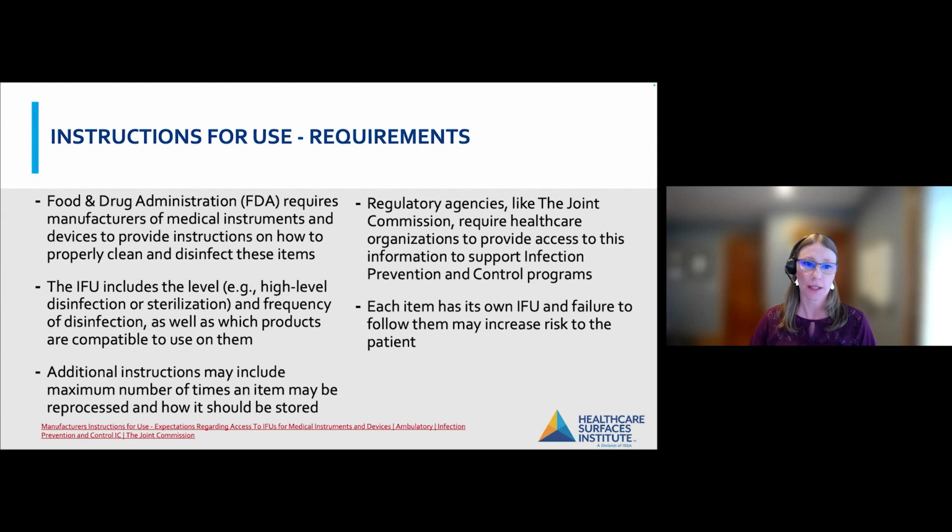There's a specific endoscope called a duodenoscope. You may have seen that there were outbreaks, and continue to be outbreaks, related to these scopes. It's because there's a channel and a little mechanism inside of them that makes it really difficult for it to be cleaned effectively. And the biofilm that Linda was talking about just a minute ago forms in that section.